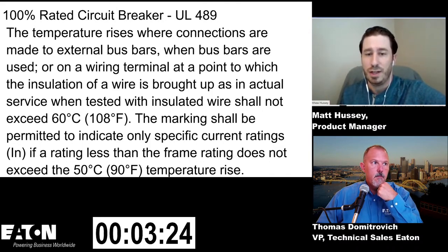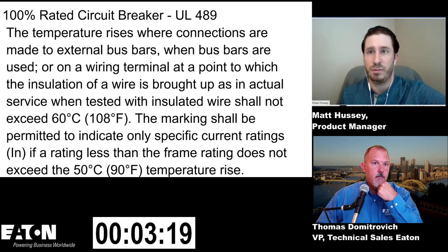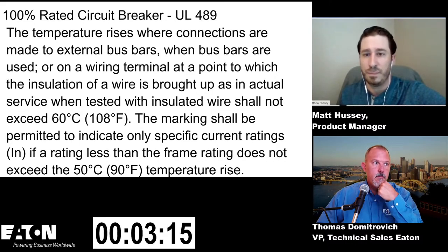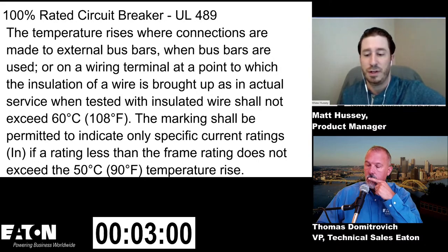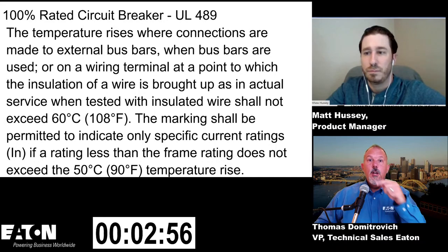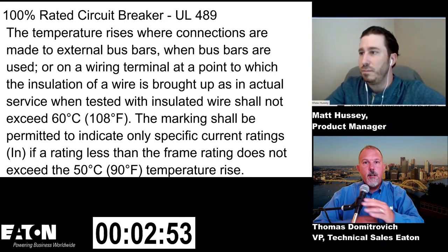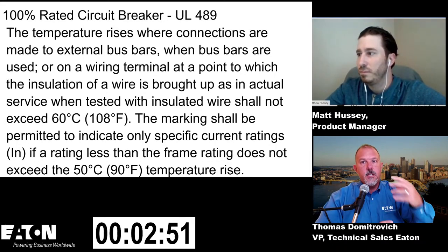C for reference. That added together creates a 105 degree C, which often mirrors the temperature rating of cabling or insulation on the cable. So usually all these temperature limits are meant to keep things from deteriorating that might create an arcing fault, and also to make sure the device performs as it's intended. Okay, so we're worried about the temperature on certain parts of the assembly, right?